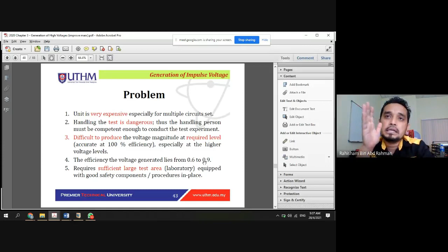If you can see here, the efficiency varies from 0.6 to 0.9. It means that if we want to generate the output voltage at 100 kV, we might end up with the output voltage only at 60 kV, or maybe 70 kV, or maybe 90 kV, or maybe 95 kV, and even maybe 110, 120 overshoot. It is very difficult to obtain the desired value. This is what is meant by the efficiency being about 0.6 to 0.9. It can be plus minus. It could be lower and it could be higher. If you set it to be 100 kilovolt output of impulse, you might end up with 60, maybe 50, or maybe 150, or maybe 120.